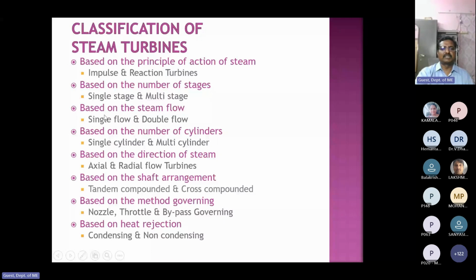Based on steam flow, the classification is single flow and double flow. Single flow means steam enters one end and leaves at the other end. Those are called single flow turbines. And where steam enters at the middle and flows in both directions, that is called a double flow turbine. Another classification is based on the number of cylinders, single cylinder or multi-cylinder. This 210 megawatt unit is a 3-cylinder turbine. If you take 800 megawatts, they have 4 cylinders also: one HP turbine, one IP turbine, and 2 low pressure turbines.